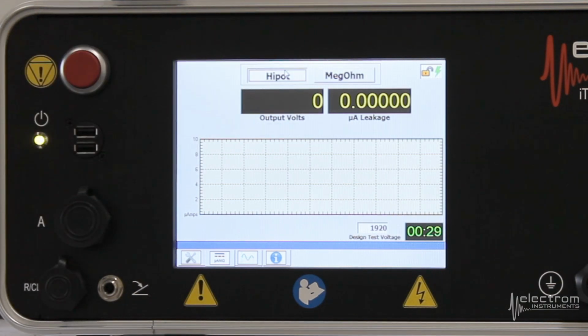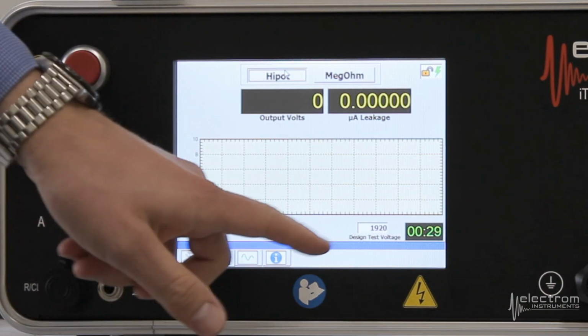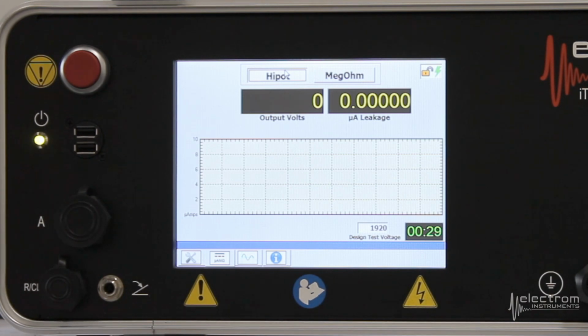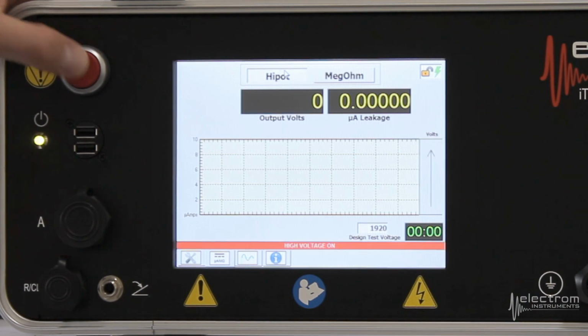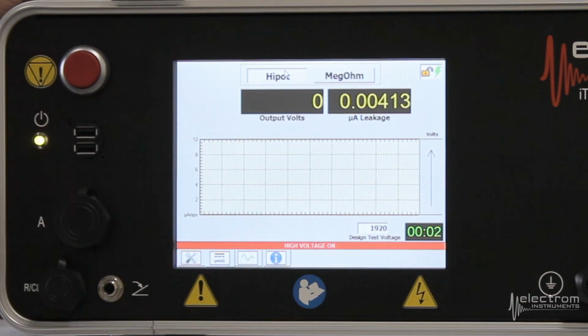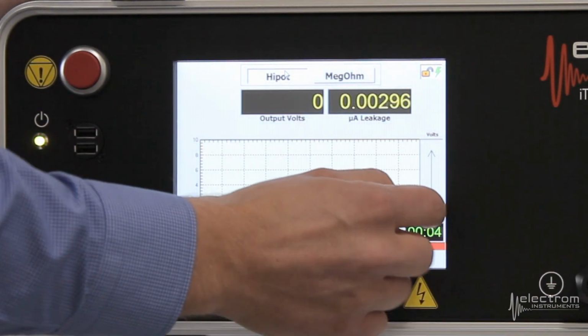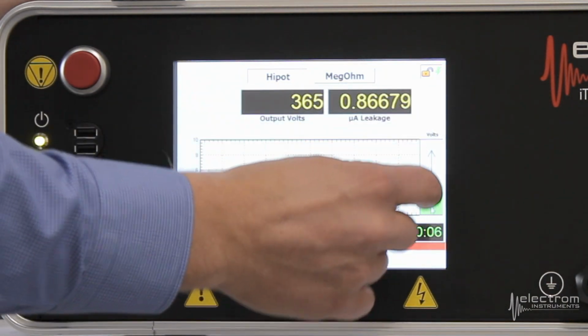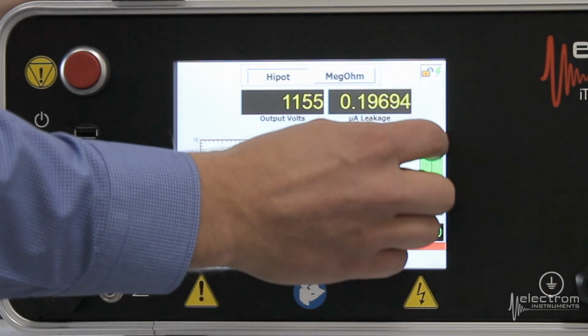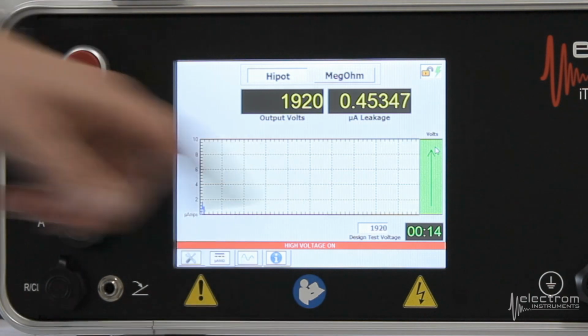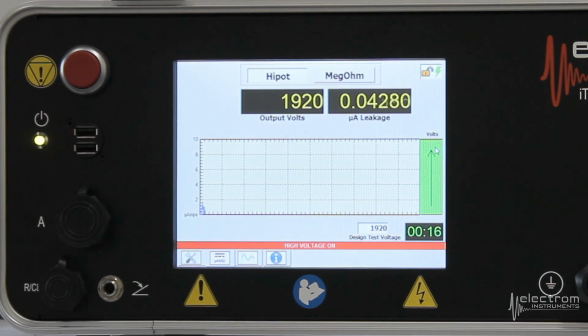So we go to the Hipot screen. Design test voltage is set to 1920. Again, you press the red button and then use your slider on the right hand side here to increase the voltage. 3 full swipes will get you to 1920, or you can go slower if you want to. You will not go higher than the design test voltage.